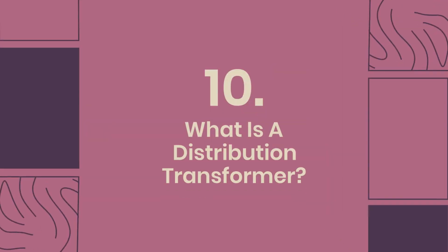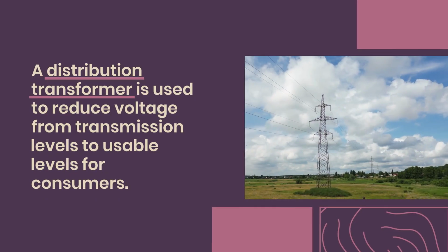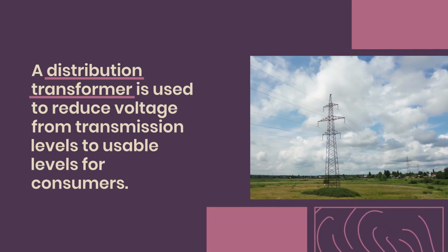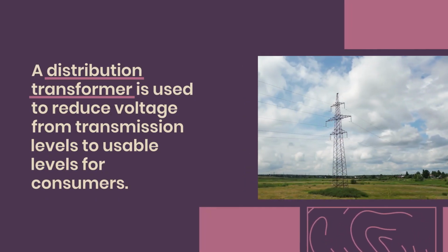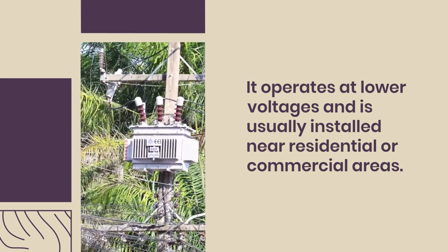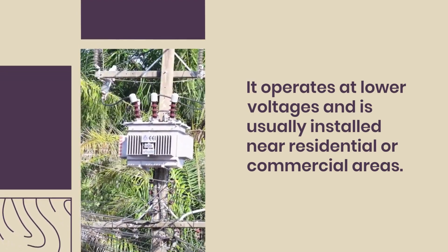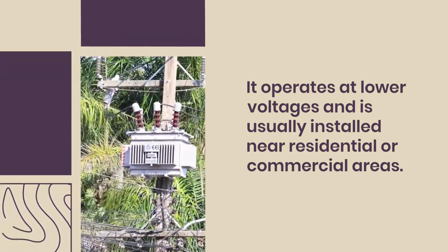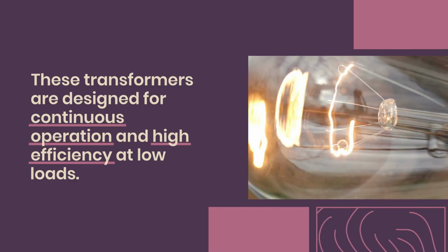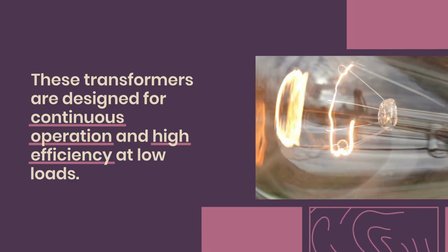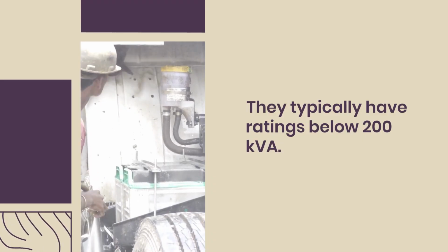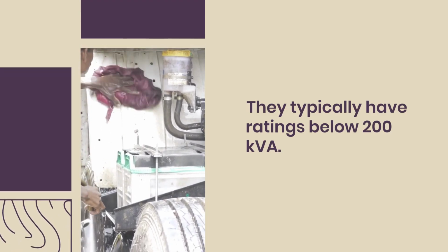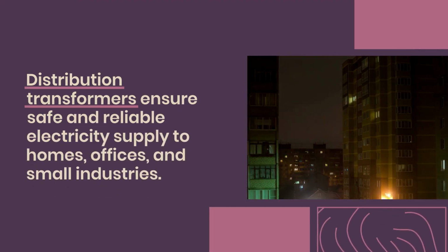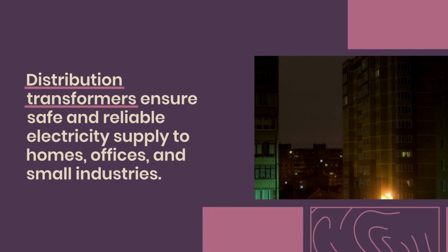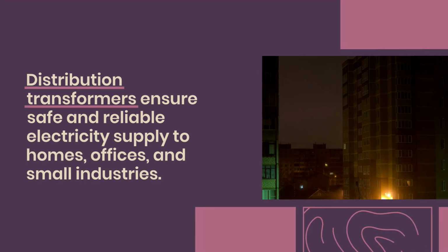10. What is a distribution transformer? A distribution transformer is used to reduce voltage from transmission levels to usable levels for consumers. It operates at lower voltages and is usually installed near residential or commercial areas. These transformers are designed for continuous operation and high efficiency at low loads. They typically have ratings below 200 kVA. Distribution transformers ensure safe and reliable electricity supply to homes, offices, and small industries.